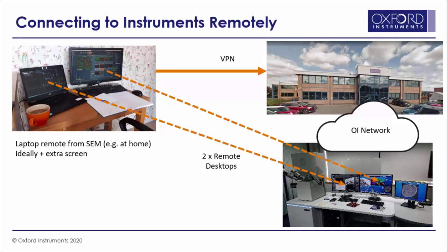Another major advantage of connecting your Aztec system to the internet is that it can then be supported remotely. With our OI Sentinel product, which includes an online performance monitoring functionality, performance information from your detector is automatically uploaded to the cloud, providing us with the history of your detector, allowing us to diagnose any problems faster and making reaching a solution far quicker and easier. This upload of data is only on detector parameters and does not share any information whatsoever on the data that you are collecting. If support is needed, then it is delivered via LiveAssist, a live augmented reality remote session, as well as traditional TeamViewer remote control of the PC with one of our experts back in the office.